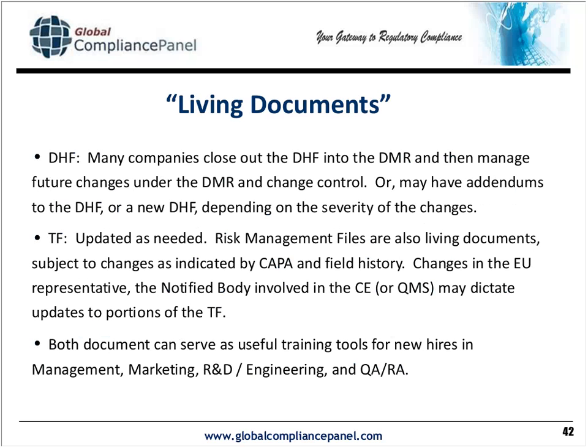The design history file depends on how you define it as to whether it stays a living document or whether it's closed out. The technical file is, in fact, a living document. And the bottom point is a key point, I feel. These documents can be useful as training tools because they and the risk documents provide a really good description of how the product got where it is, what the issues are, etc.